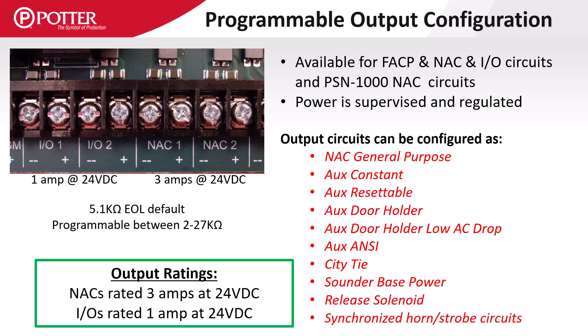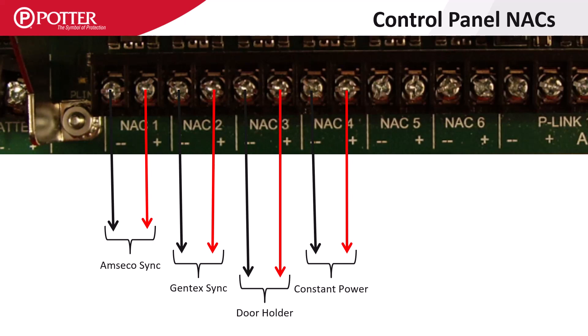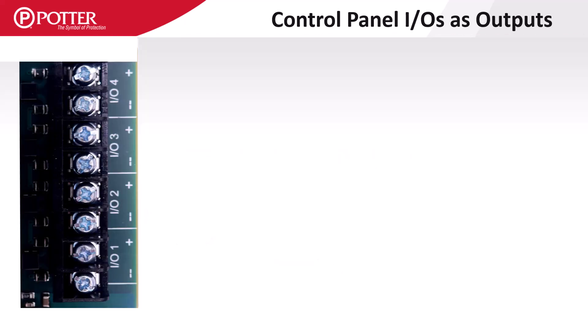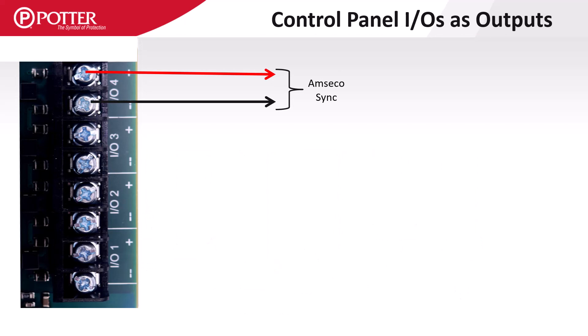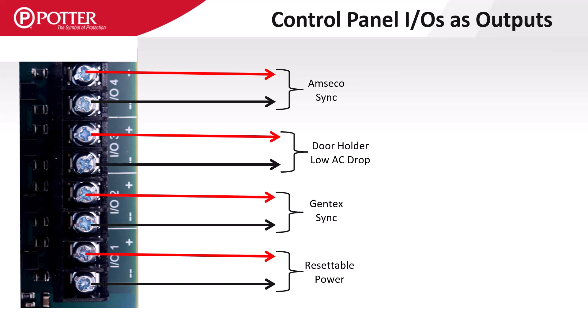All NAC or IO outputs can be configured to use either the Potter standard 5.1k end of line resistor, or can be programmed with a value between 2 and 27k ohm. All NAC circuits are independently programmable with the capability of assigning each a different function. The same ability to independently program outputs is available on the IO circuits. IOs can only be wired Class B.